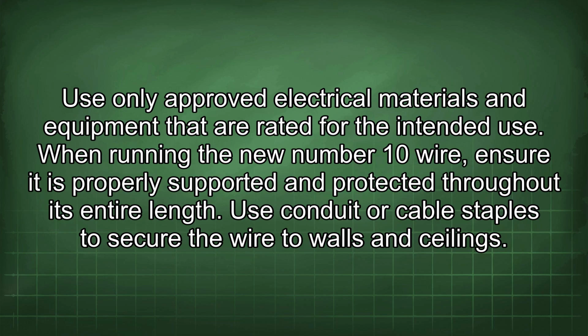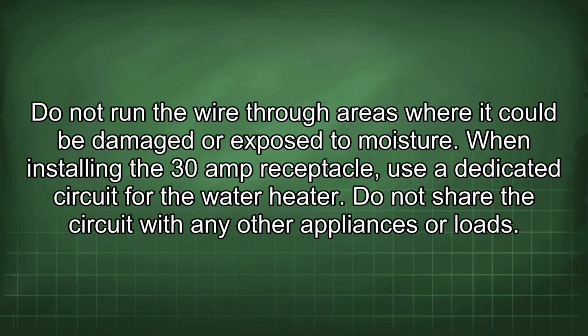When running the new number 10 wire, ensure it is properly supported and protected throughout its entire length. Use conduit or cable staples to secure the wire to walls and ceilings. Do not run the wire through areas where it could be damaged or exposed to moisture.